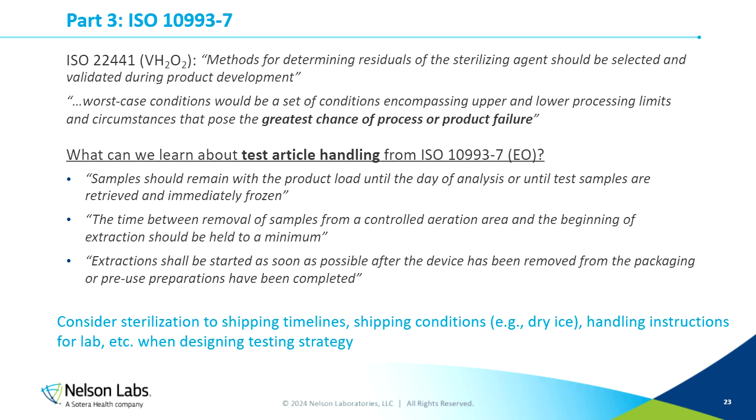If you think of it in practical terms, if your device could be sterilized and then walk down a hallway and exposed to a patient the next day, it doesn't make much sense to sterilize a device, have it sit on the shelf for 2 months, ship it in an uncontrolled way, and test it later, because that gives the sterilant a massive opportunity to decompose or evaporate, and it wouldn't be representative of a worst case patient exposure. So it's a good idea to have a plan for how to justify the time between sterilizing and testing.